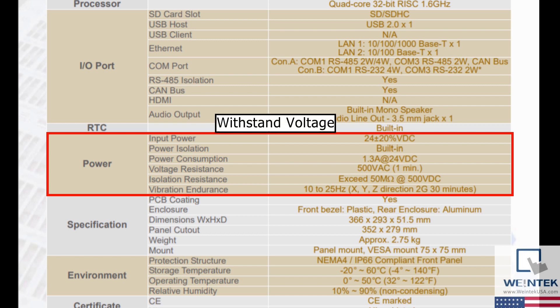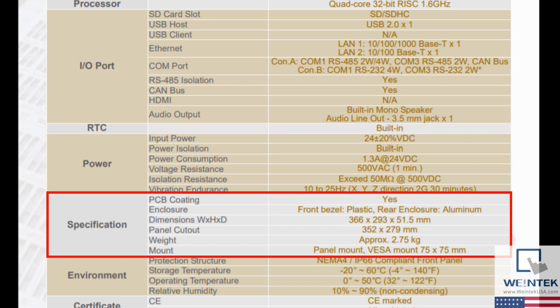This voltage resistance is also called withstand voltage in the industry. Isolation resistance shows the limit to resistance of the flow of electrical current, which is 50MΩ at 500V direct current. The vibration resistance is how much vibration the unit can withstand. For the 3152X, it is 10 to 25 Hz in the X, Y, and Z direction at 2 times gravity for 30 minutes.